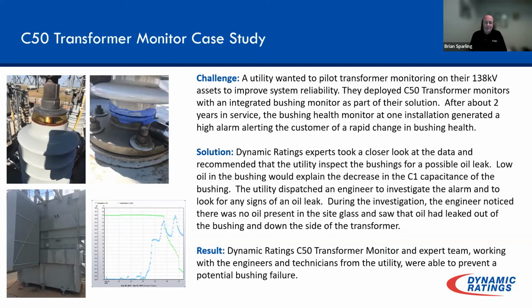And so they sent out an engineer to go and check it out. And here you can see when he got on site, there was no oil to be seen in the reservoir at the top of the bushing. And there was this large stain of oil leaking down the side of the tank as the evidence. And when the outage was taken before, somebody had tried to do something about stopping the leak on the bushing, but that didn't work out very well. So in this case, it was no choice. They replaced the bushing and put it back in service.